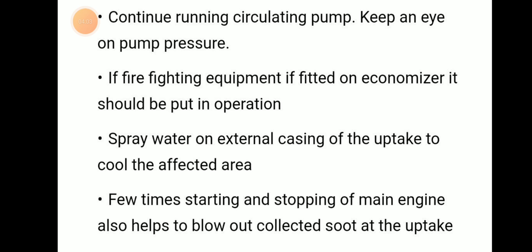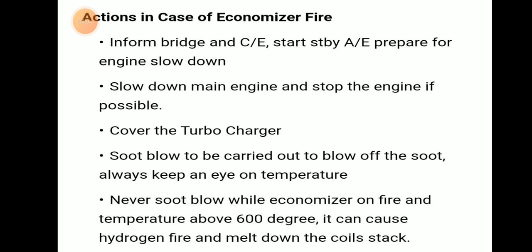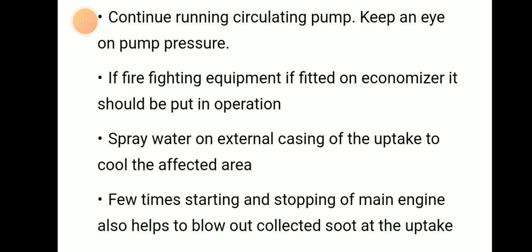Continue running the circulating pump and keep an eye on the pump pressure, whether it is varying or not. If firefighting equipment is fitted on the economizer, it should be put into operation and spray water on the external casing of the uptake to cool the affected area.